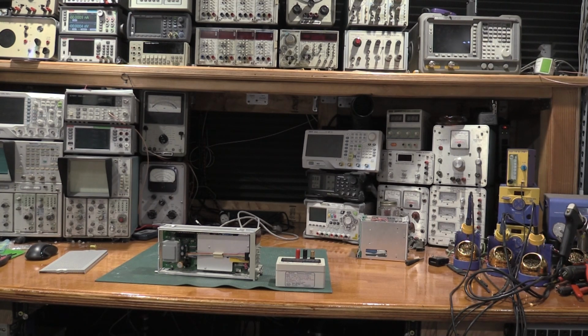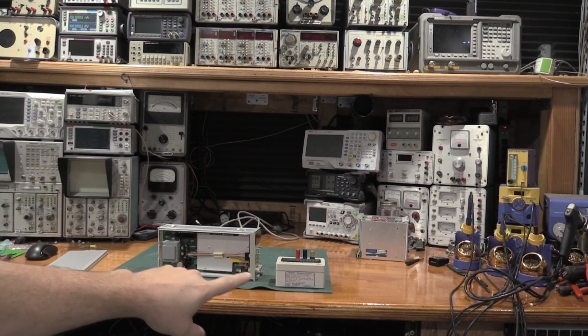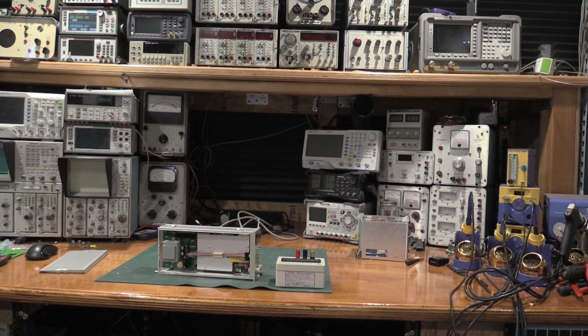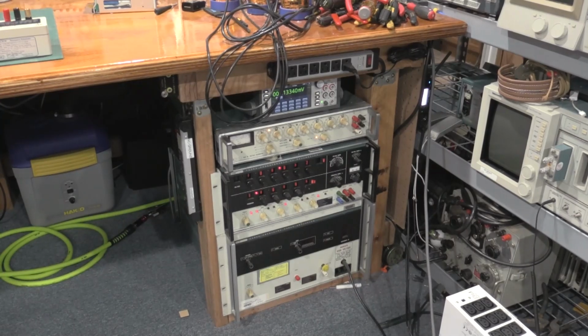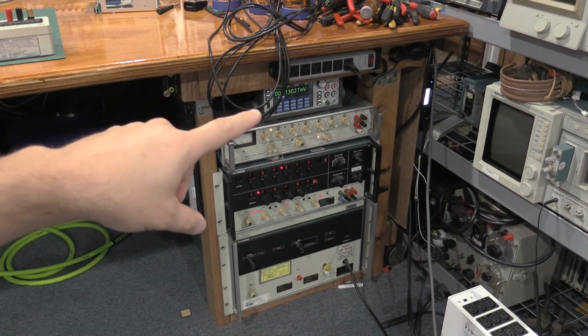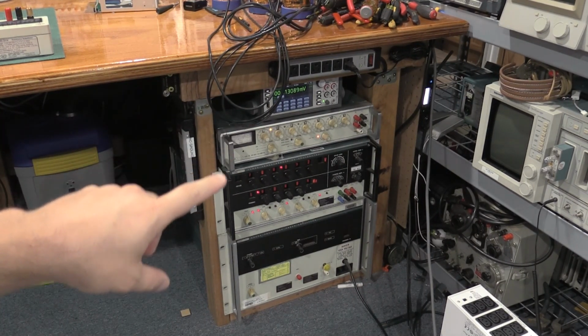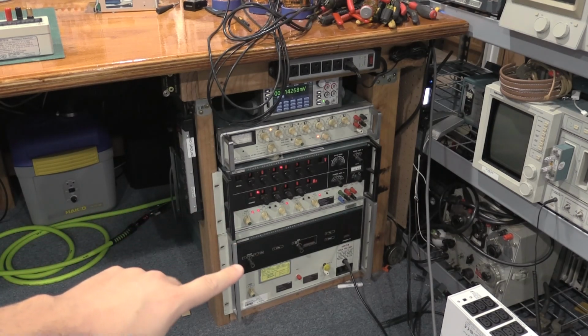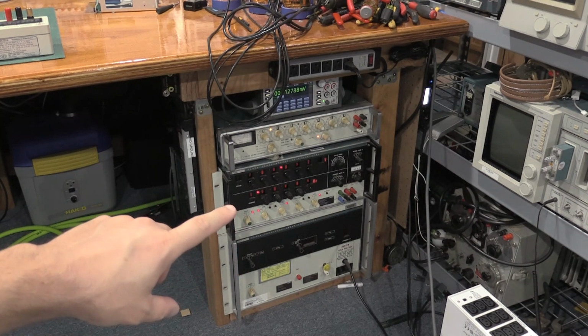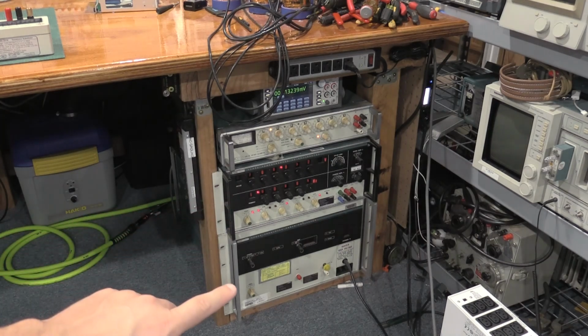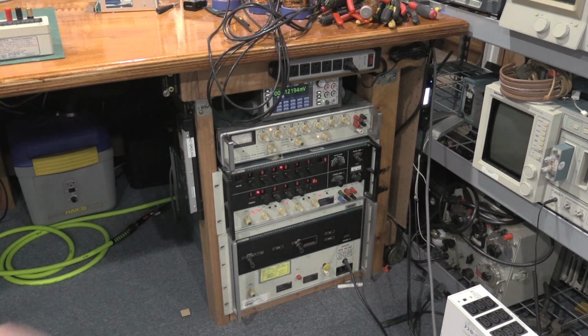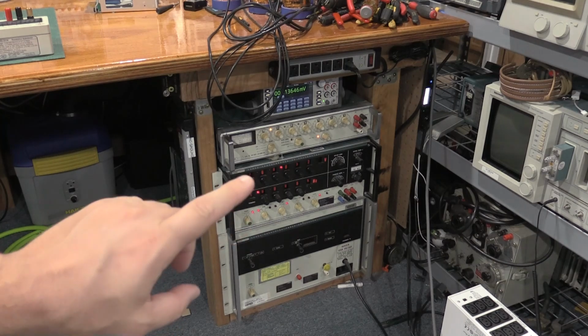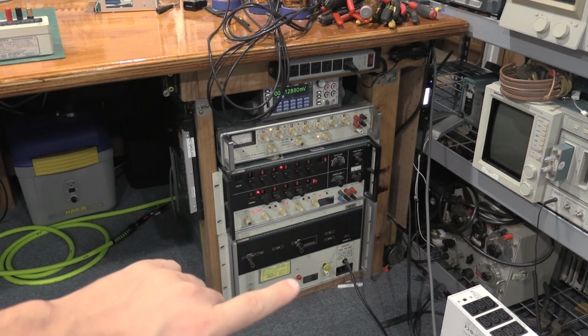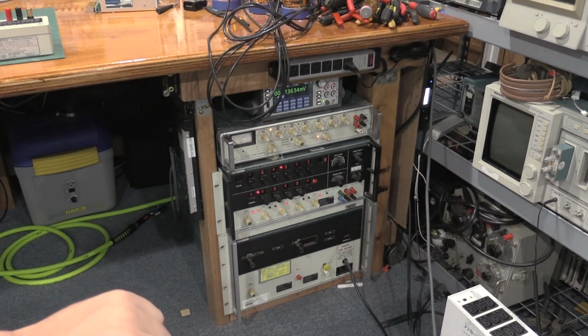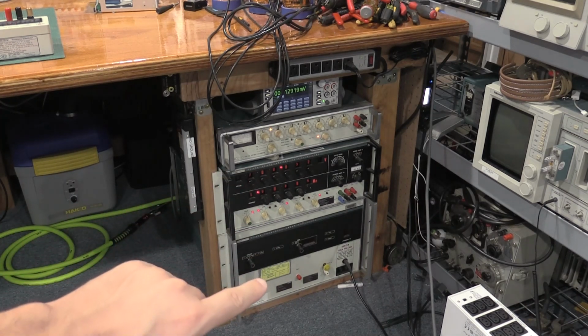We have the source measure unit up here, resistance box here, coming down. We have this alignment and calibration stack here. There's the 7.5 digit meter, DC supply, AC amplifier. That'll do 1500 volts. That does up to 100. And that unit controls that unit through an interconnecting cable. If you don't have the interconnecting cable, there's a port on the front where you can still use the amplifier, but it's really nice to put the amplifier in remote control.